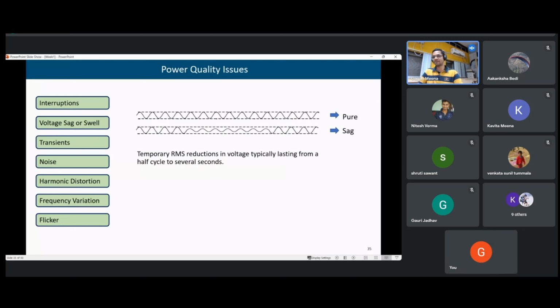There are specific standards for this too - for how much duration it should last to be termed a voltage sag, and what the amplitude should be. Usually it is below 0.9 per unit. If the voltage goes below 0.9 per unit for a few cycles, it is termed voltage sag. And if it goes beyond 1.1 per unit, it is called voltage swell.